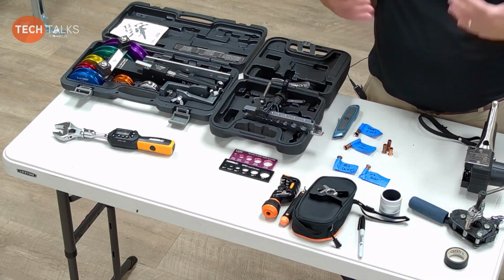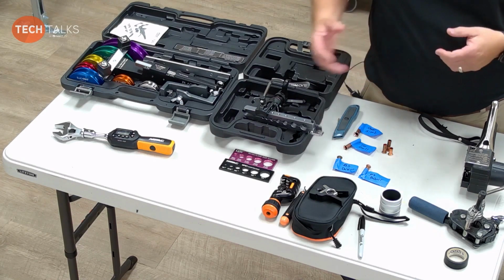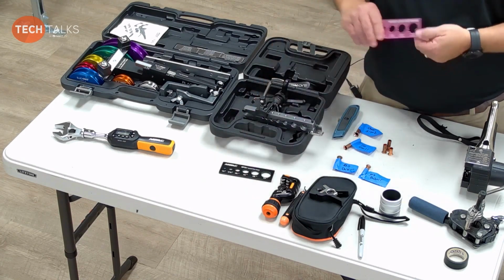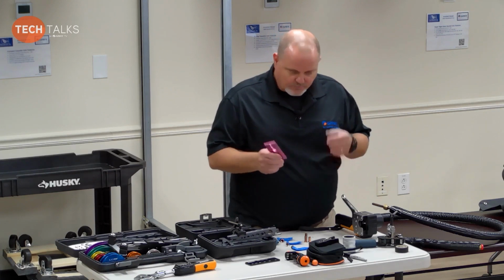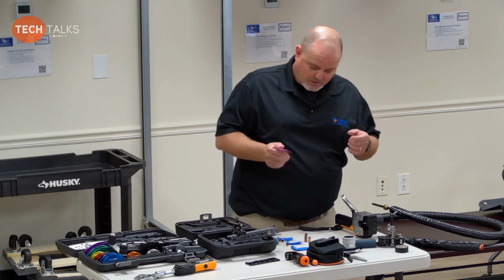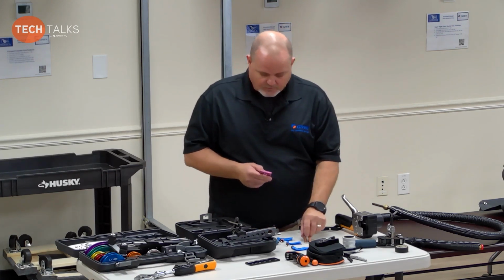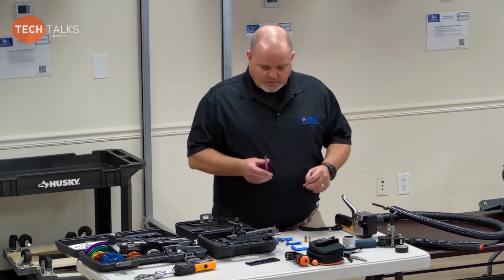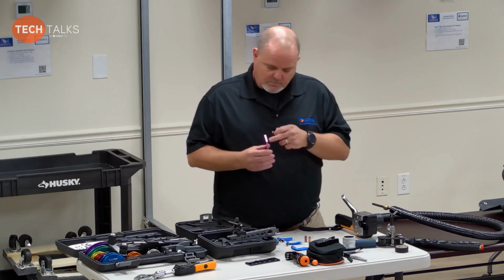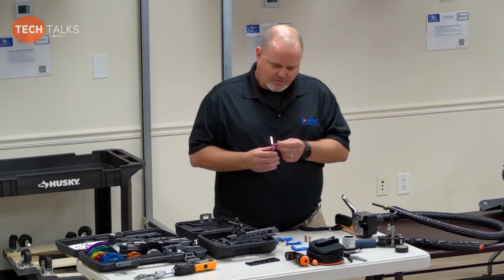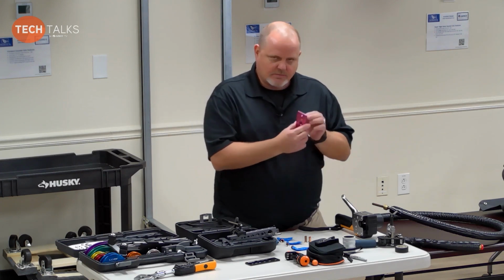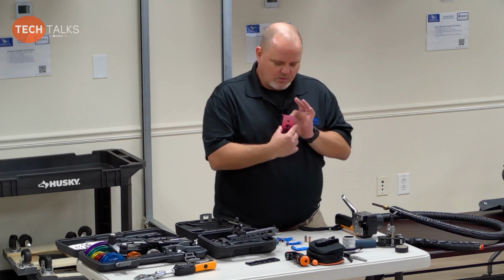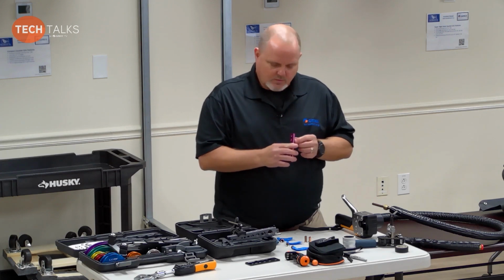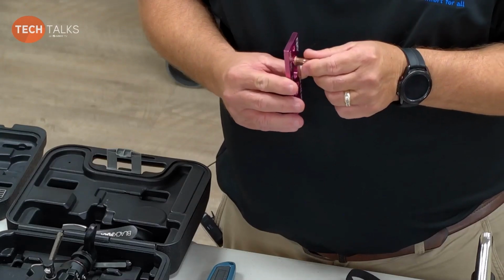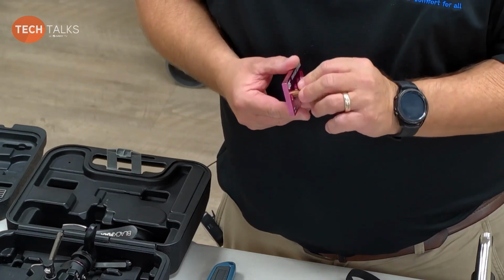The only thing that matters is the quality of the flare - it has to be made properly, and I highly recommend using a flare gauge to check your flares. I've got an example of a perfectly good flare here. This flare block has a little ring stop inside it - when you push the flare in, it should stop and not go all the way through. If it goes all the way through, the flare was made too small. If it won't go in at all, the flare is too big. That's something to be mindful of.